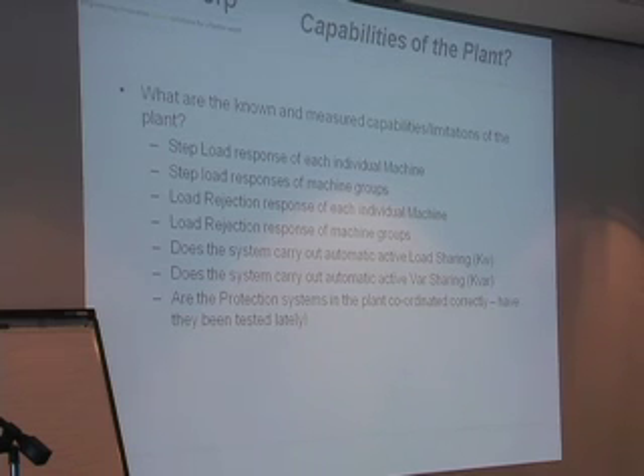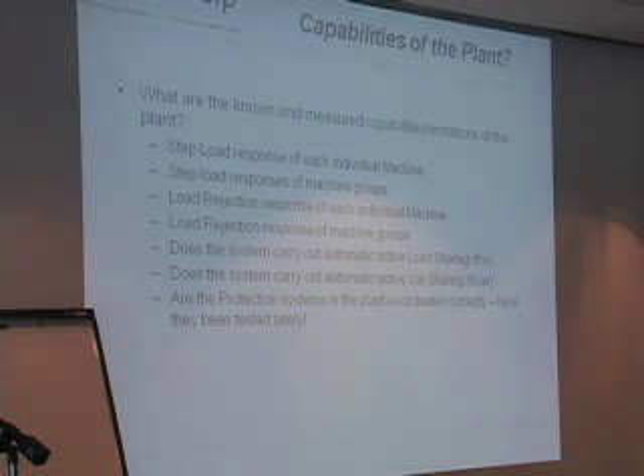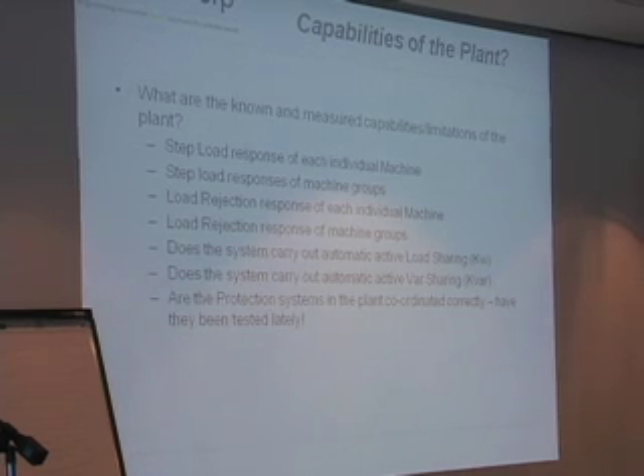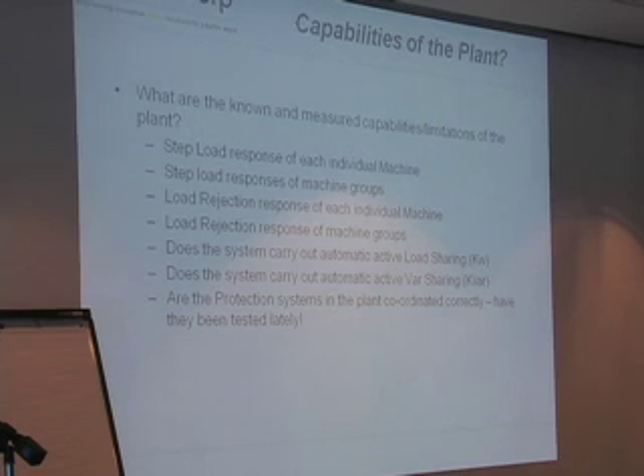Different standards need to apply depending on location, whether it's some regulatory body dictating how long the system's allowed to run at a lower frequency or voltage than rated, or how the feeders are going to trip out. Do they have feeder load shedding if the power station starts to struggle with low frequency or low voltage? Especially when you bolt on a big wind turbine or renewable resource that was never intended in the original design, will you start tripping feeders or protection because you're generating energy from different locations? That's a whole study in itself: reviewing the existing protection and planning something that works with your new design, integrating the renewables.